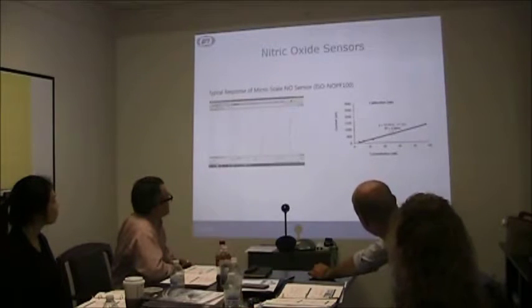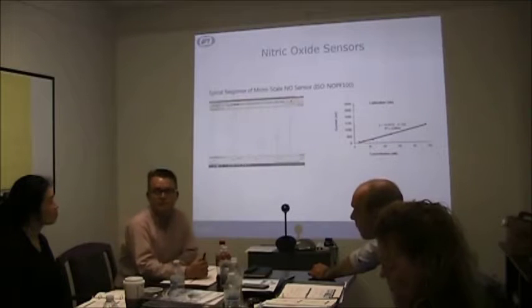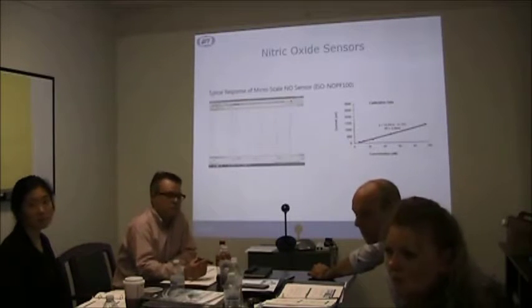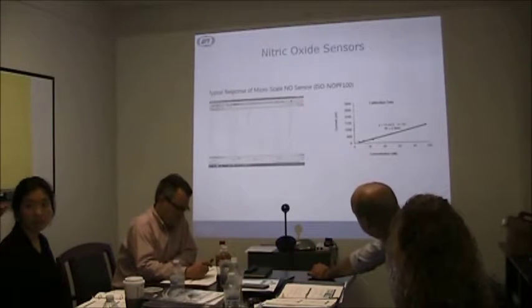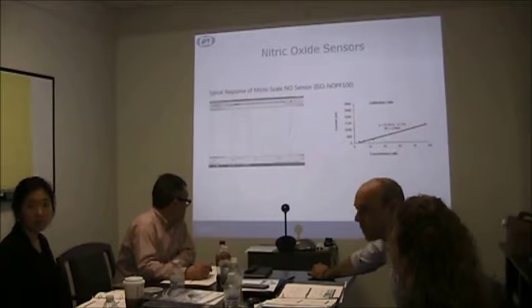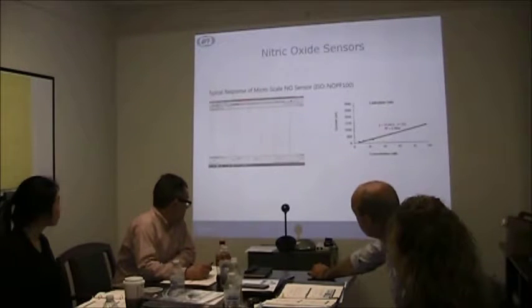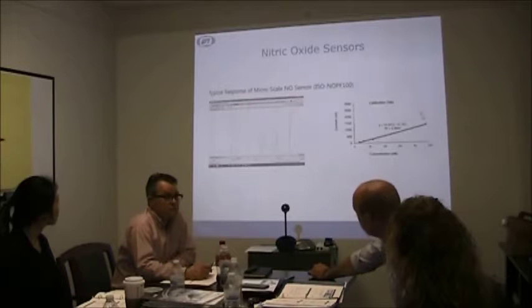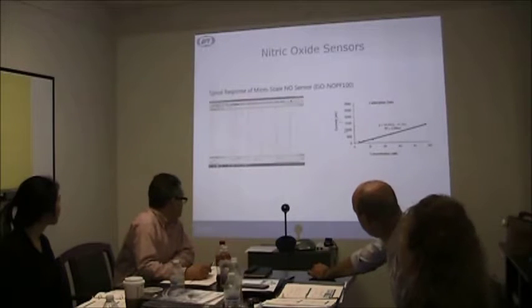Again, over here, you can see that this is obviously a much more sensitive version of the 2 millimeter ISONOP, so we have a larger value here. So somebody wanting to detect very low nanomolar concentrations, this would be the sensor to choose as opposed to the 2 millimeter ISONOP, because if you need to measure really low concentrations, this is going to get you the sensitivity you want. Is concentration on the y-axis then?